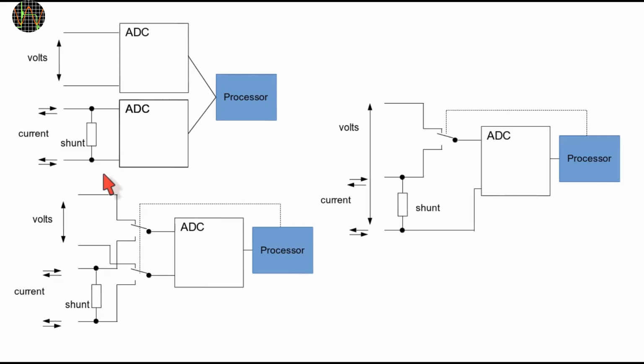There are 3 ways to do this. The first one on the upper left uses 2 separate ADCs, one for each channel. They can be optimized for their job. The voltage one to measure the relatively large input voltage of say 10 to 20 volts, while the other one needs to measure the voltage drop over a shunt resistor, typically in the range of say 100 to 200 millivolts maximum. The ADCs could be set to measure differential, meaning we could allow positive and negative values.